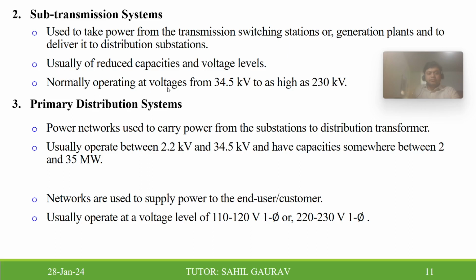The sub-transmission system has an operating voltage range from 34.5 kV to as high as 230 kV. The primary distribution system carries power from the substation to the distribution transformer, and its operating voltage range is 2.2 kV to 34.5 kV, with capacity between 2 and 35 megawatt. The secondary distribution system supplies power to individual customers and usually operates at 110 to 120 volts single phase or 220 to 230 volts single phase.